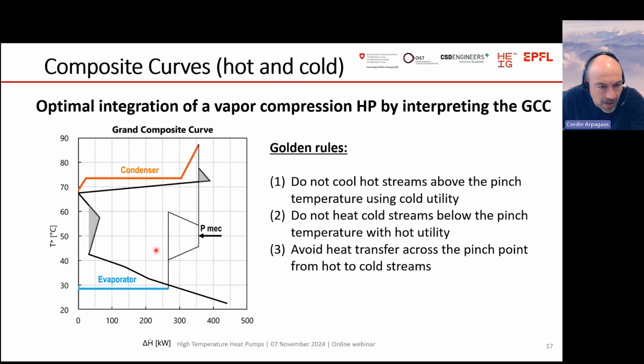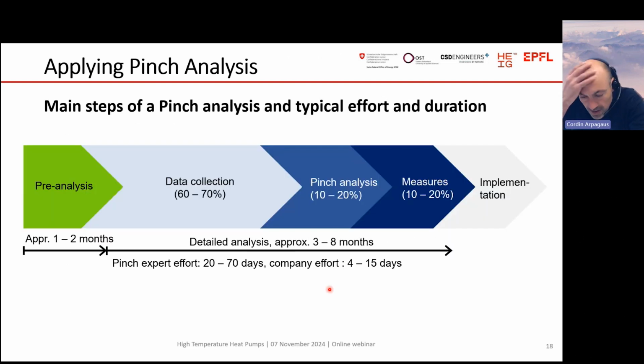It's a very simplified example, but it shows the main rules to integrate the heat pump across the pinch: not to cool hot streams above the pinch, not to heat cold streams below the pinch, and to avoid heat transfer across the pinch from hot to cold. In Switzerland, we can do pinch analysis with some funding from the Swiss Federal Office of Energy.